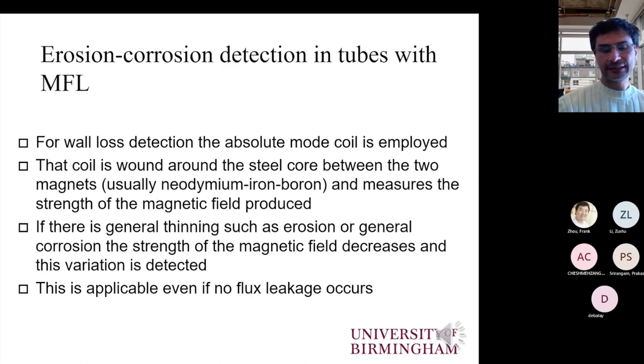So as I said earlier, in MFL, we have two types of coils. The absolute mode coil is employed for general wall loss instead of the differential coils. The differential coils are the ones that are used for the smaller defects, for the pitting corrosion and potentially for cracks. The magnets are typically based on rare earth, so neodymium, iron, boron, or samarium cobalt are the types of magnets that are typically used.